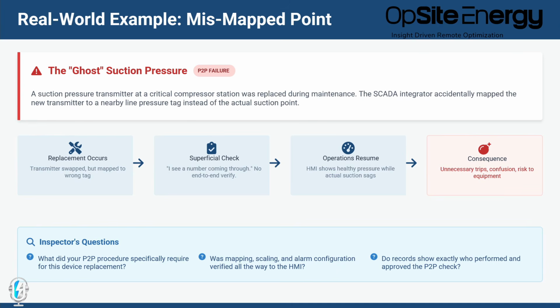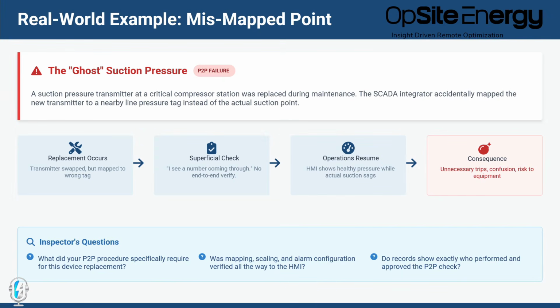So in this real-world example, let's get specific. In this one, you're talking about a situation where a suction pressure transmitter at a compressor station was replaced during maintenance, and the integrator mapped the new transmitter to a nearby line pressure instead of the actual suction point.